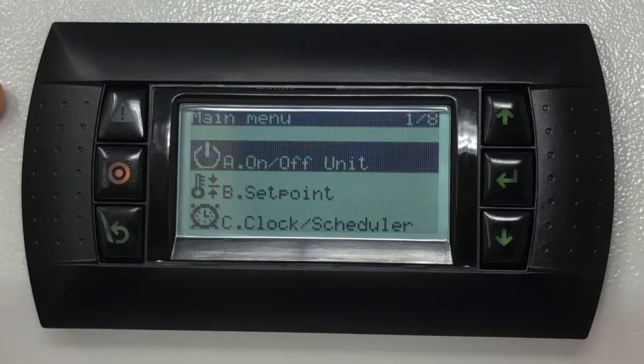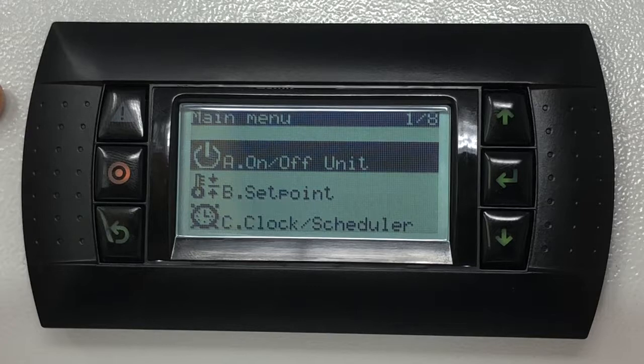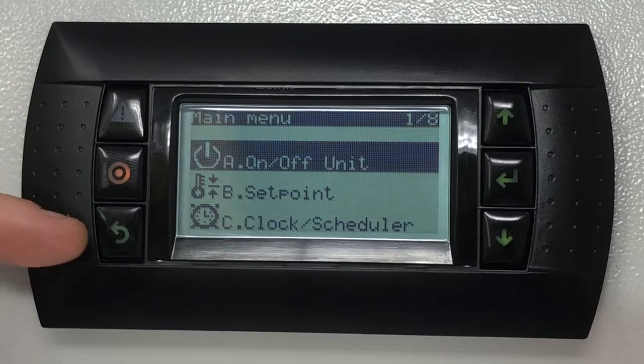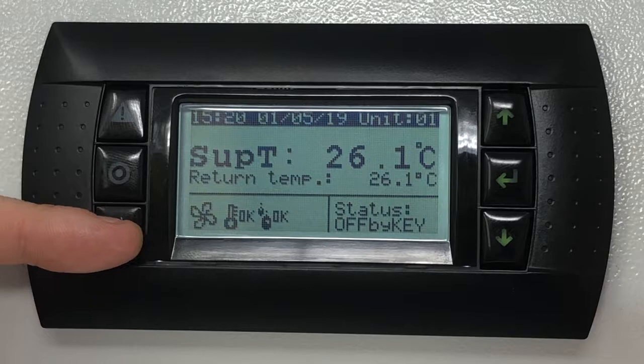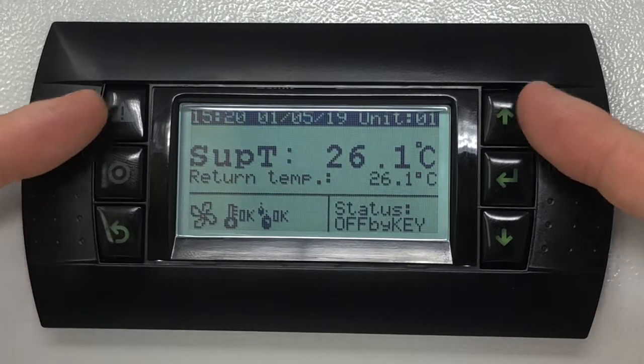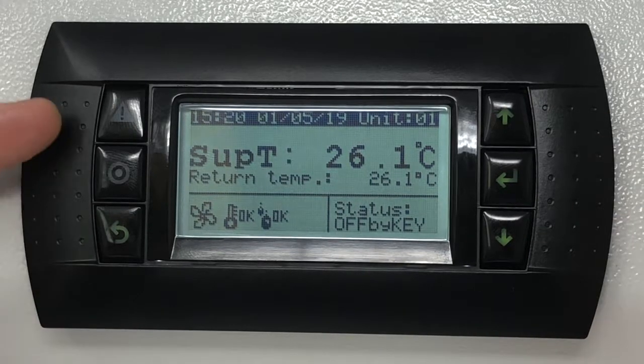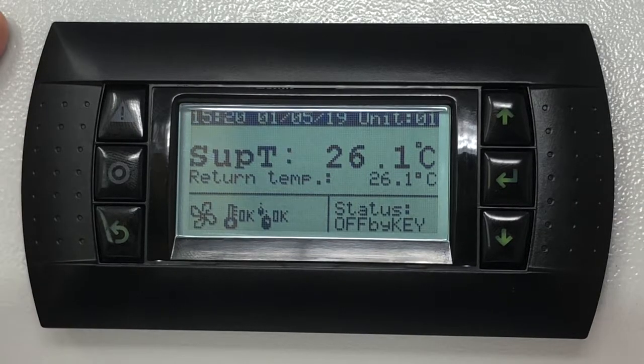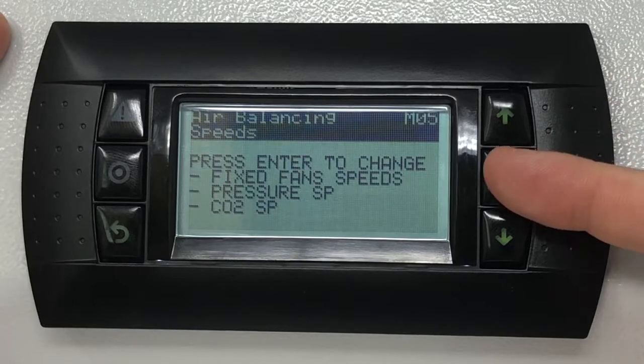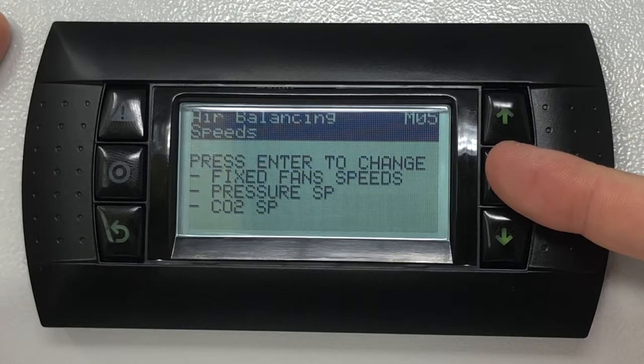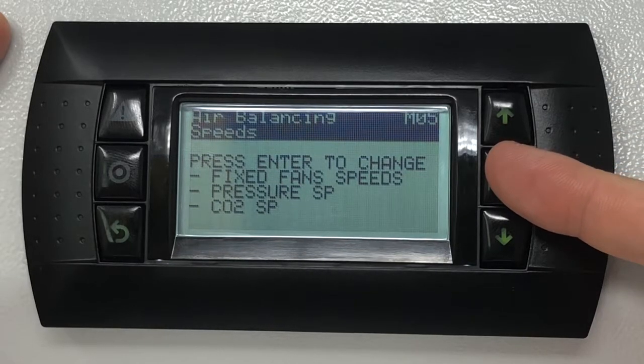To adjust these minimum and maximum fan speed settings, press the escape button on the bottom left hand side of the display a few times to make sure you return back to the home screen. Press the up key once to display the air balancing speed screen, marked as M05 on the top right hand corner.